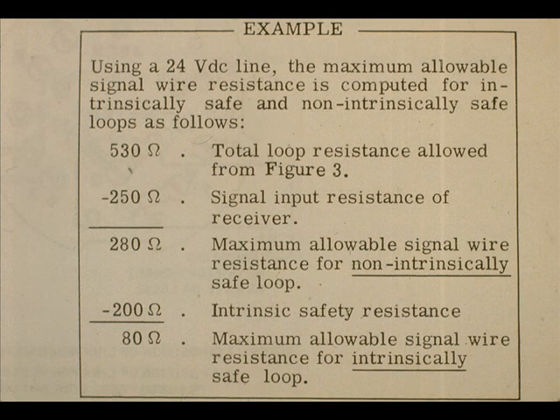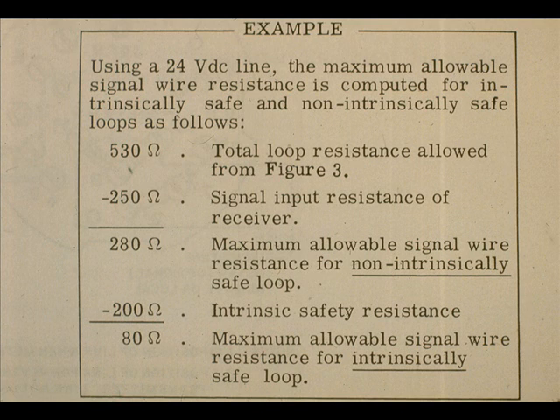For an intrinsically safe loop, an additional 200 ohms is added to the receiver. 530 ohms minus 450 ohms leaves 80 ohms maximum for the signal wire resistance.